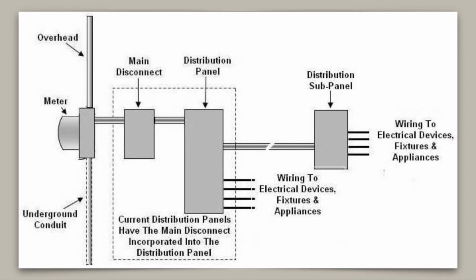A distribution box, also known as a subpanel, is an electrical component that expands the circuit breaker capacity. This is the preferred method when expanding a main panel's capacity. Normally, the subpanel is installed next to the main panel, in which one of the slots on the main becomes the main breaker for the subpanel. For example, this breaker may be a 30, 40, 50, or 60 amp breaker. Therefore, the subpanel does not need a main disconnect since the breaker in the main panel is protecting the subpanel.